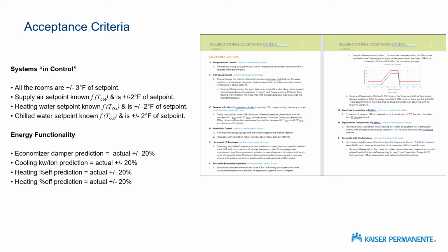The important part of this whole acceptance criteria thing is that we need to define system performance in a set of acceptance criteria. And these have got to be in the project documentation. We want to see them in project specifications, typically the control spec. We have one design engineer who's putting these directly onto the plans so that they're right in the construction documents. We also need to see these in the commissioning plans. They need to be hard contract requirements. And we really need to identify the points that need to be trended in order to validate the system.